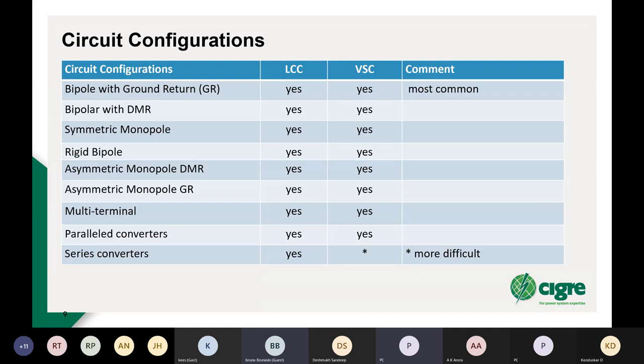So looking at what kind of circuit configurations are possible with each of the technologies, LCC and VSC, you can see that if you do a comparison, bipole with ground return is available in both technologies. It's the most common configuration for HVDC and LCC. In VSC, the most common configuration till now has been a symmetric monopole, but that is also changing as the power ratings go up, and I think bipolar with ground return or bipolar with DMR may become the more common technologies.